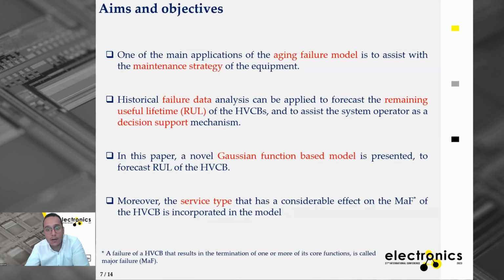So what are the aims and objectives of this research? First, we need to know that an aging failure model would be helpful for maintenance strategy. In this work, I'm going to use historical data to estimate the remaining useful lifetime of the circuit breaker, which would assist the system operator in decision making. What we used is a Gaussian function-based model, and we incorporated service type, since as shown in the previous figure, it has a considerable effect on the major failure rate.